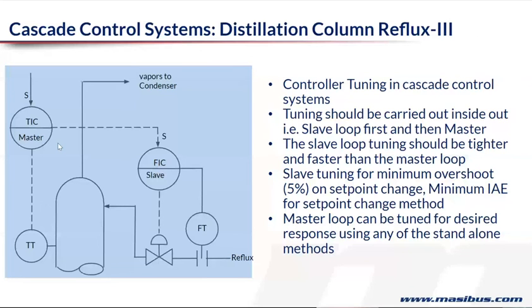And once you have tuned this, you tune the master with the same method and logic you use as a standalone, right? So this is also very logical. First tune your slave, then go and tune the master. Okay. Sometimes you have to give priority to the slave. In normal life, the master always has the priority, but here the slave has the priority. Okay, which is good.